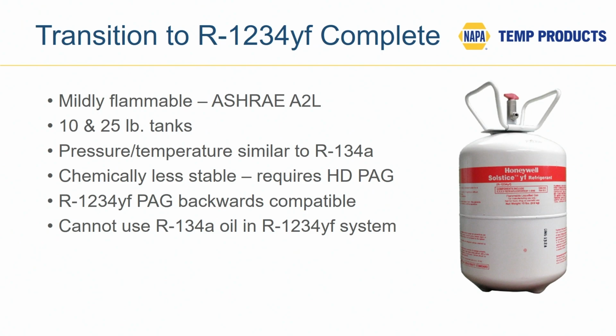The downside, and we'll discuss it in a little bit more detail shortly, is that the molecule is chemically quite unstable compared to R134A, and that can lead to some service issues, as we shall see. The oil does call for heavy-duty PAG oil. The good news is that the new oils for R1234YF are backwards compatible with our old R134A systems if it is the same viscosity. But just to reiterate, you can't use the old R134A PAG oils in a new R1234YF system.